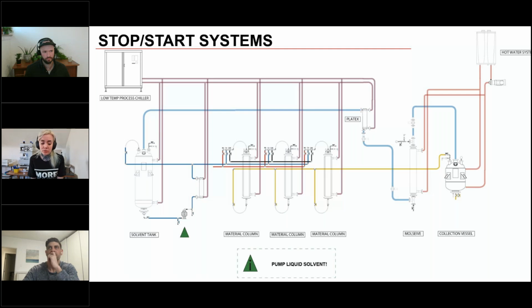And so, nitrogen is a great tool, but it shouldn't be a crutch that you use instead of a leg. You want to support your process with it and not use it to replace a recovery pump. It's not sort of nitrogen or pump, it's thermodynamic control and pressure differential supported by those other two items wherever it can be.